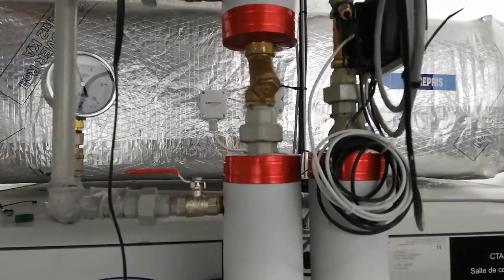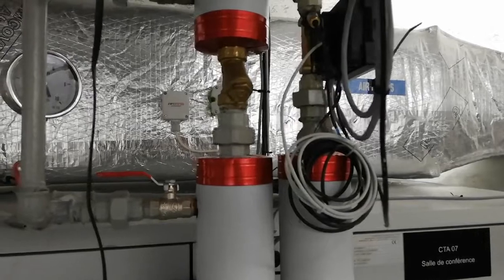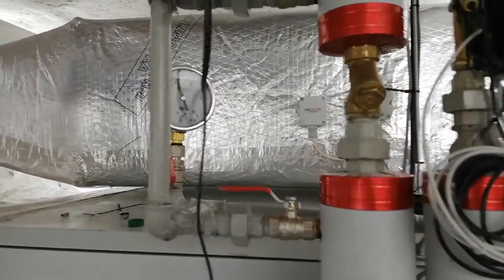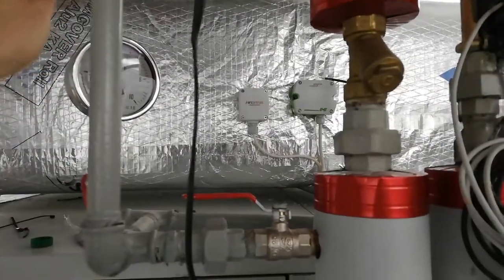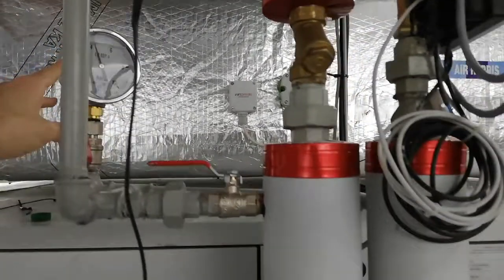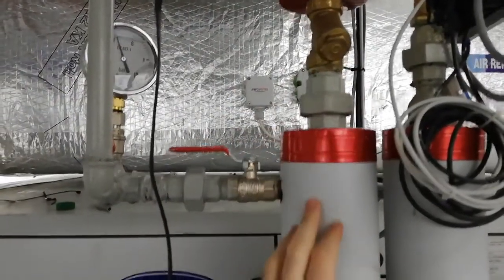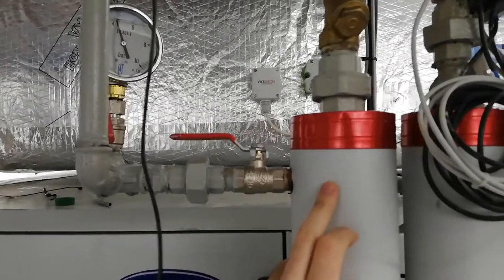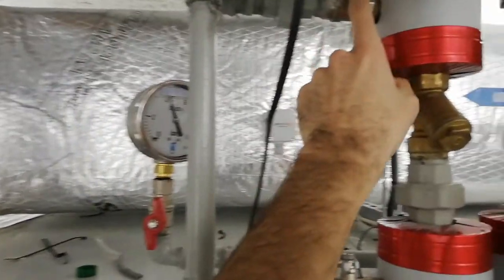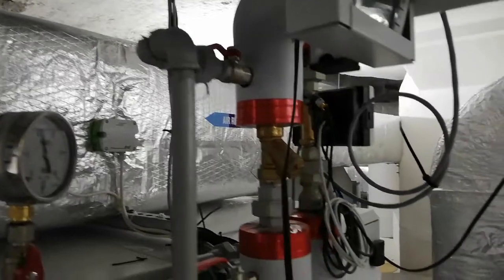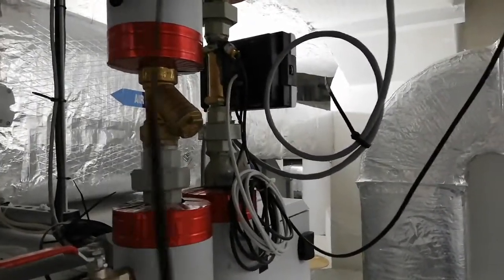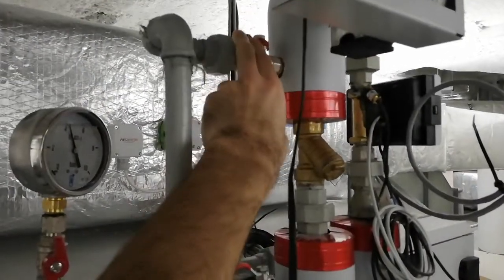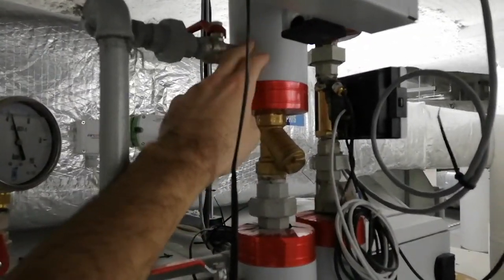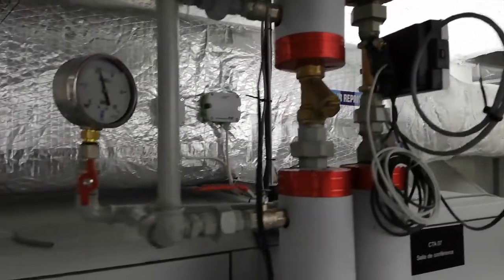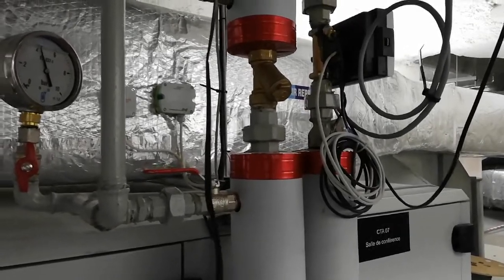If the pressure drop is too high, the strainer won't be efficient anymore. So what you need to do is install a pressure gauge, like here you have one. This pressure gauge has to be able to monitor the pressure drop through the strainer. If you want to measure the pressure upstream of the strainer, you just open this valve and you close this one. So you will be able to measure the pressure here. Then you do the same: you close this one and you open this one, and you will be able to measure the pressure here. Then you check the pressure drop. If the pressure drop is too high, it means that you need to clean the strainer.